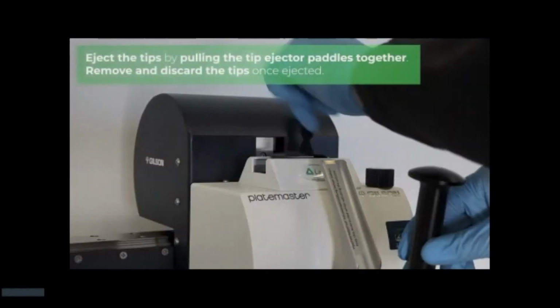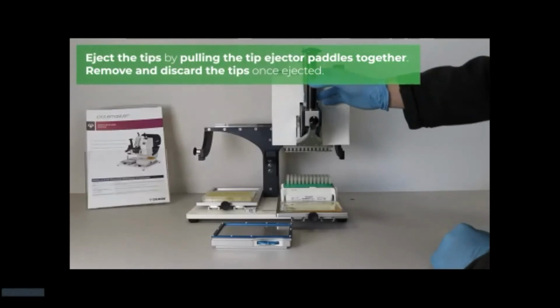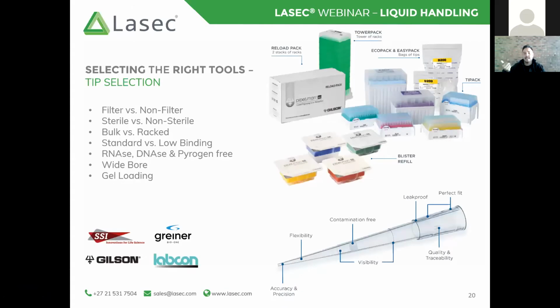So in terms of a pipetting cycle, we have now only used one aspiration step and one dispensing step, thereby avoiding the need for 96 steps, 8 steps, or 12 steps. That machine can also be used for your 384 well plates, completing it in 4 steps. Essentially what I wanted to get across is that it is really important, depending on what pipetting task you are doing, to ensure that you are using the right pipette or tools that are more beneficial to your process.